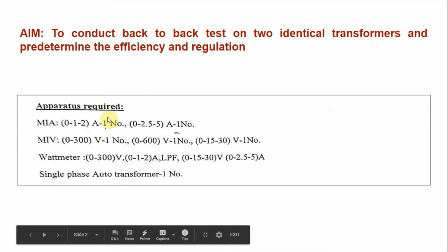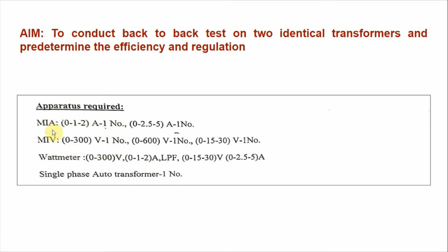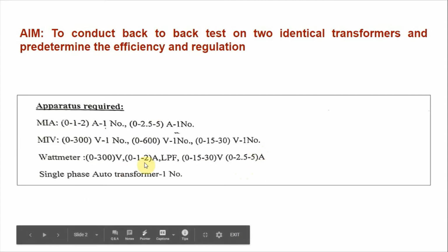The 0 to 2 amps ammeter, 0 to 300 volts voltmeter, and LPF wattmeter are required for OC calculations. I'll repeat again: the 0 to 2 amps ammeter, 0 to 300 volts voltmeter, and LPF wattmeter are used for the OC test. The 0 to 5 amps ammeter, 0 to 30 volts voltmeter and UPF wattmeter are used for the SC test. So this is the circuit diagram.